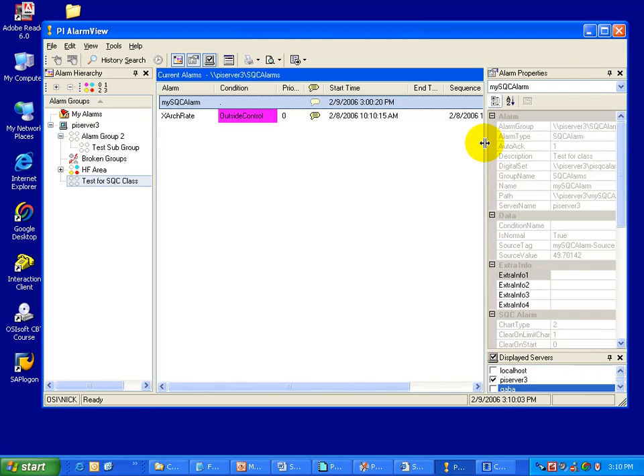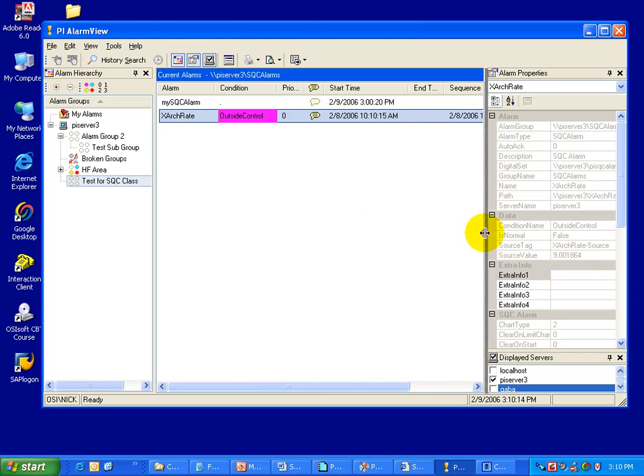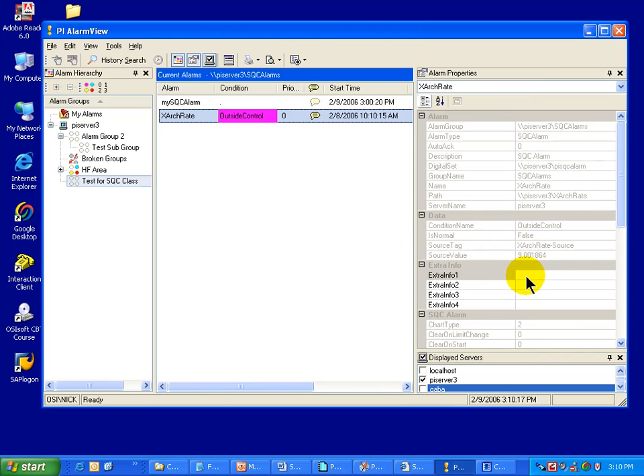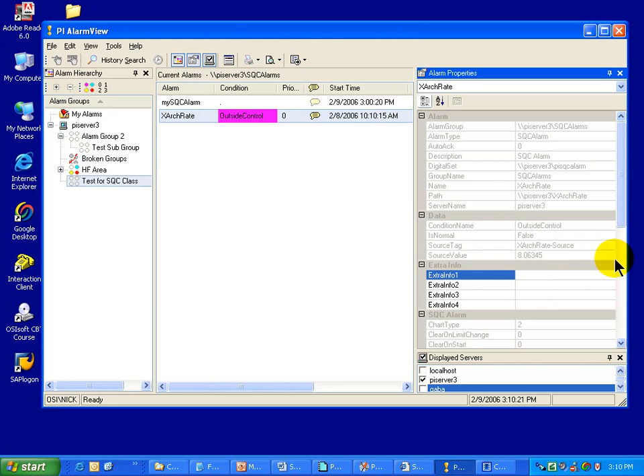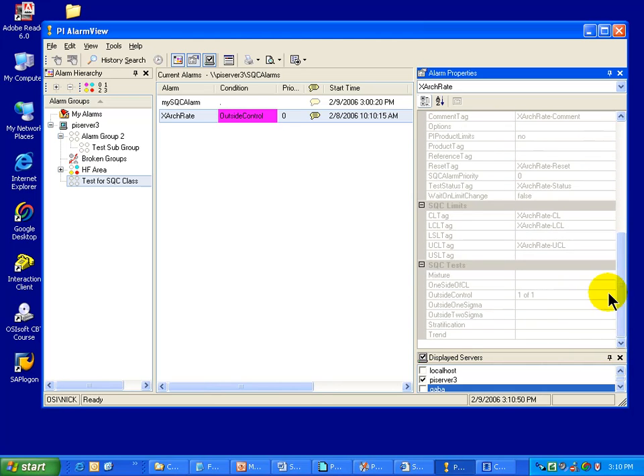Over on the right-hand side, there is the option to show Alarm Properties, which you can turn on and off by choosing View > Alarm Properties. When I select an alarm, I can see all the things associated with it — for example, the Extra Info field where we can enter a website URL. This panel also shows other details about the alarm: the Alarm Group it belongs to, the Digital State Set it uses, its current condition, the condition of the source value, what the source tag is, and the tags representing the control limits.